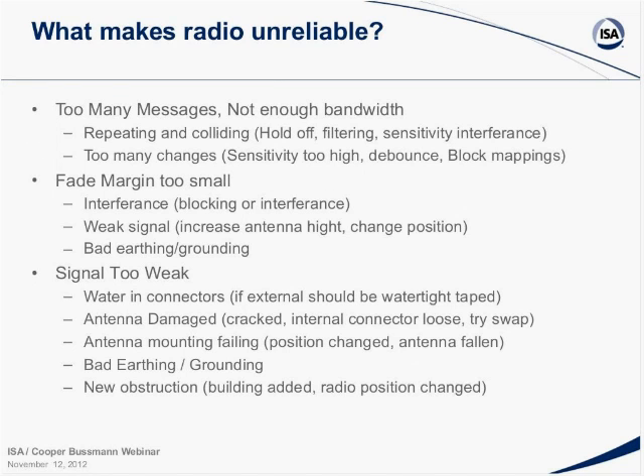If you don't have enough bandwidth, the first thing you'll see is collisions, certainly with Ethernet, because that uses CSMA, carrier sense multiple access. Another cause of too many messages is having your update rate set too high, or sensitivity too high, on a process transmitter. One important setting for a wireless transmitter is how much bandwidth or deadband you set before you say the process has changed.